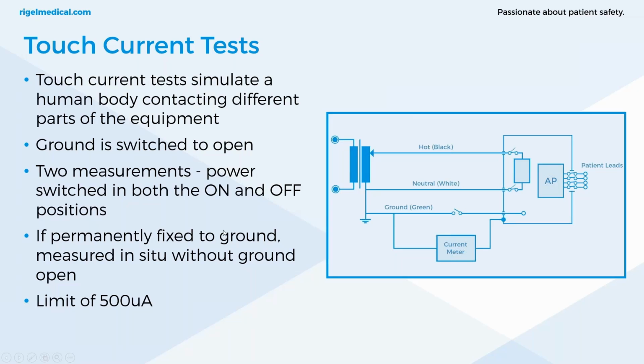on and off. If the appliance is permanently fixed to ground, touch leakage is just performed in situ without ground open. So you're just putting the probe onto the medical device that's fixed to measure the leakage that way. And this has a limit of 500 microamps. There is a table at the end which does highlight that.